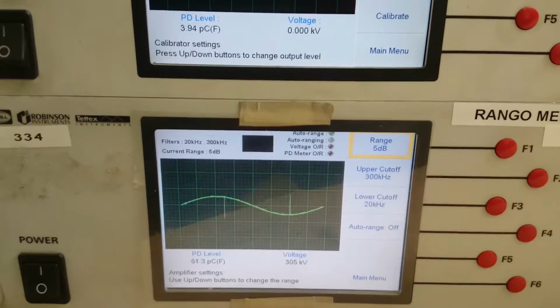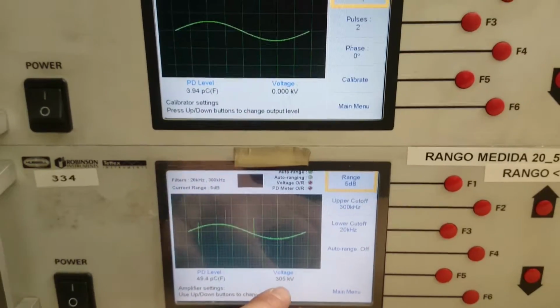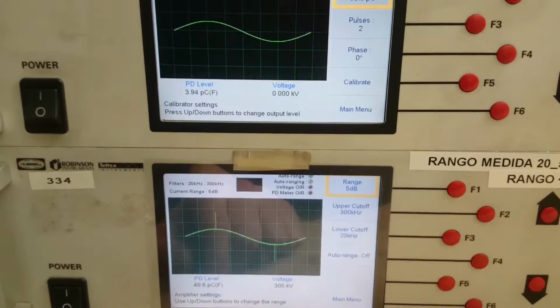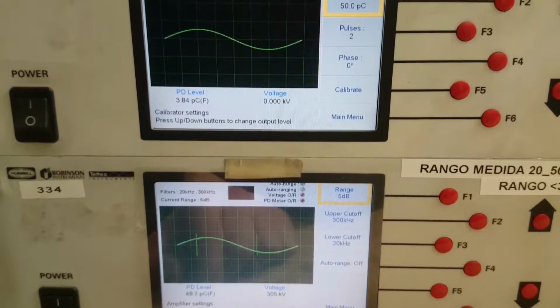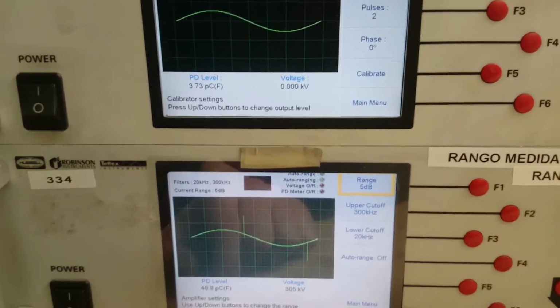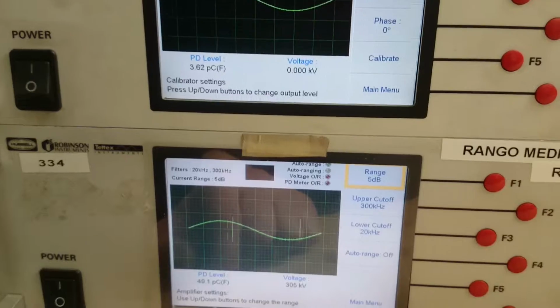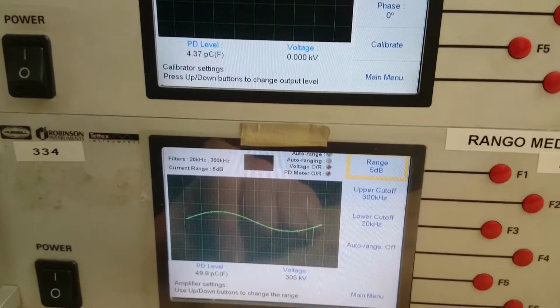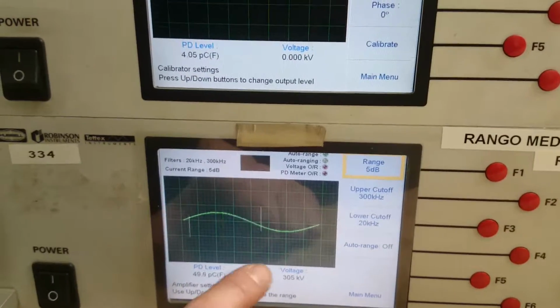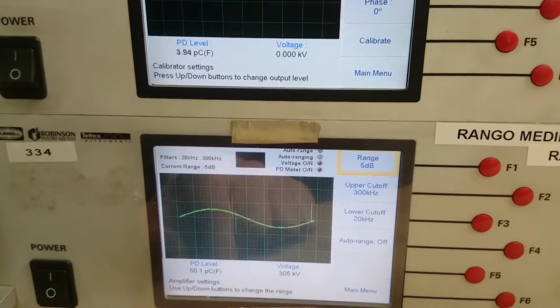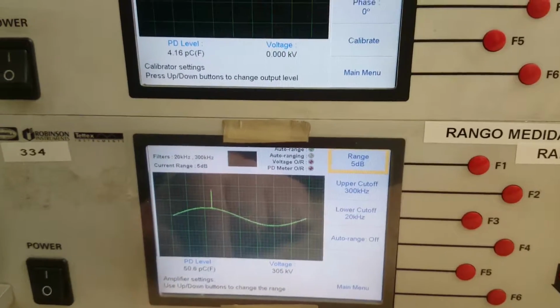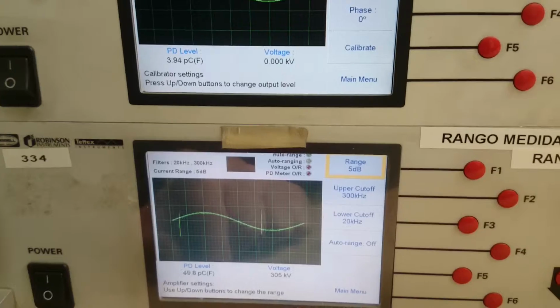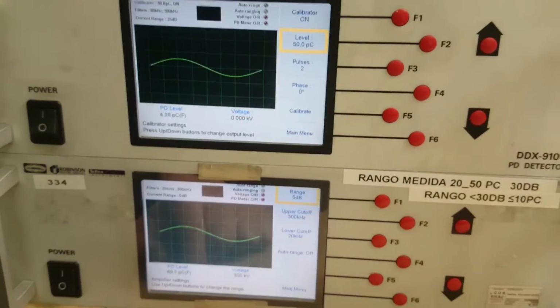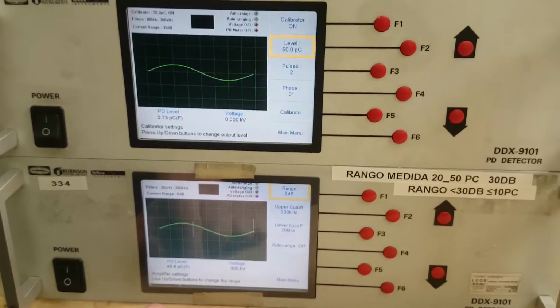So as I sweep the frequency on the kilovolt meter here, the pulses will reference to the new frequency, which means when you're testing a transformer at 400 Hz or 200 Hz or whatever, it will reference to that 400 Hz, it won't reference to the 50. So that's just checking that's correct. So the ranges are correct, the calibration is correct, and also the input reference is correct. That's all working.